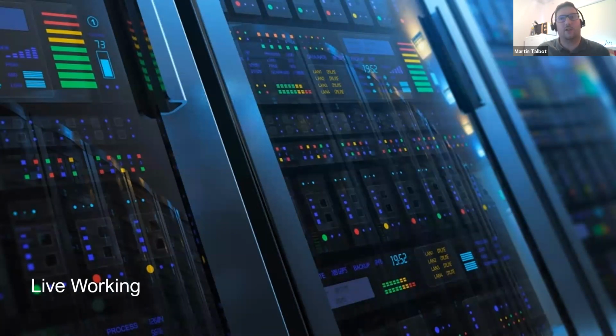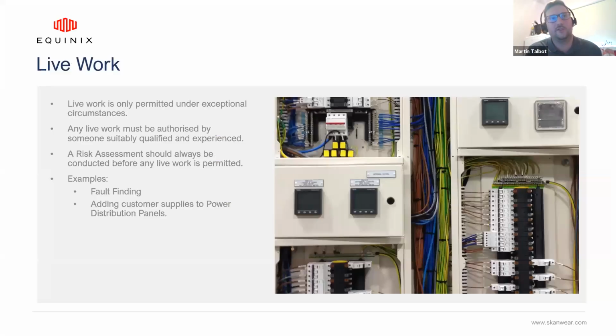I just want to look at some live working aspects that might be present in data centers. So live work is only permitted under exceptional circumstances, and that should be in any industry or any building. Any live work must be authorized by someone suitably qualified and experienced, and a risk assessment should always be conducted before any live work is permitted. An example is always fault finding, and the other data center specific example you might consider is terminating new customers into power distribution units.